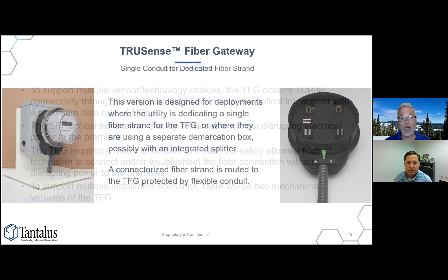The design is also such that our TRUSense fiber gateway will need a meter technician to install it, because it's going inside the meter socket behind the meter. But we've designed it so that a fiber technician can independently go to this device, connect or troubleshoot the fiber connection, without disrupting power to the premises, and they can do so safely because they're not reaching into the meter socket at all. We've also designed the device so you can easily disconnect power from the internal electronics, again without disrupting power to the home. To support multiple installation scenarios, we're going to have two versions of the TRUSense fiber gateway.